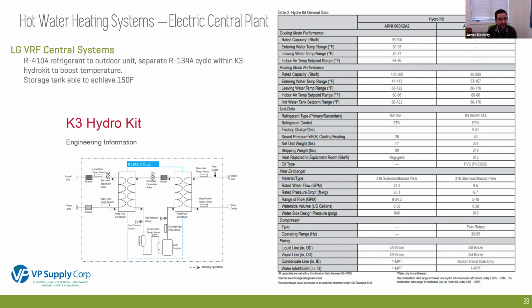So the reason, going back to Brendan's slide on the refrigerants, they're able to get both the low temperature and the high temperature in low ambient operating conditions is they actually mix both refrigerants. The R410A refrigerant runs between the outdoor unit and the hydro kit inside, and then the hydro kit inside has an additional R134A cycle that takes additional heat from that R410A and puts it into another loop. That water loop then goes to another heat exchanger that then brings the heat into the storage tank.